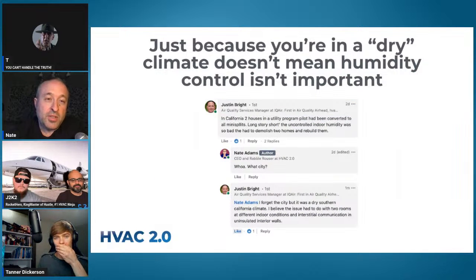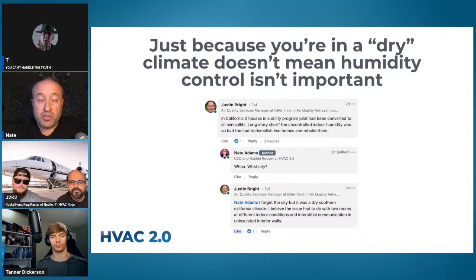This surprised me today. I posted about dehumidification, and my friend Justin Bright hopped in and said in California, two houses in a utility program pilot had been converted to all mini splits. Long story short, the uncontrolled indoor humidity was so bad they had to demolish two homes and rebuild them. I'm like, whoa, where? He said he forgets the city, but it was a dry Southern California climate. So just because you're in a dry climate doesn't mean you don't have to pay attention to humidity control—if you have a tight house where people are taking lots of showers, cooking a lot, or just have a lot of occupants, all kinds of bad stuff can happen. It's always good to pay attention.